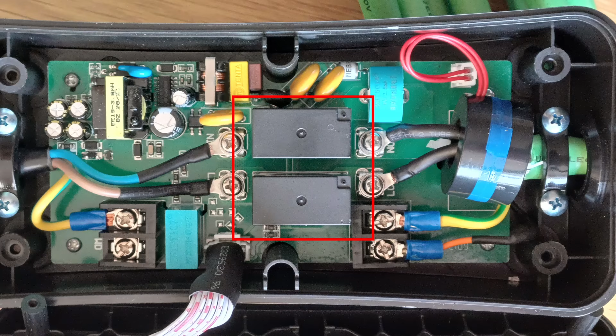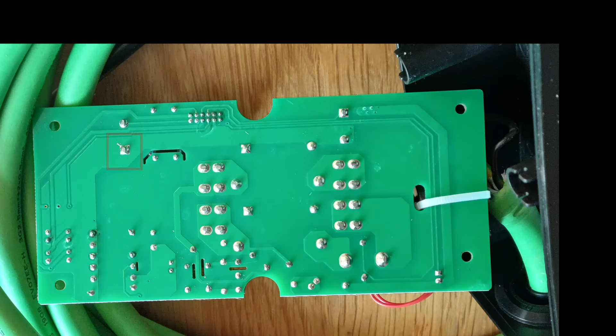The first clue is from a look at the components on the circuit board. We can see there are two relays, those two dark grey things in the centre of the board. That's not enough for pen fault protection. But to be sure, I lifted the board out and looked at the back. On the front, the earth conductors attach to screw terminals on the same side of the board, roughly in line with one another. Flip it over, and on the back we see those two terminals here and here, and they are directly connected by a track on the PCB. So from that examination we know this doesn't have pen fault protection.